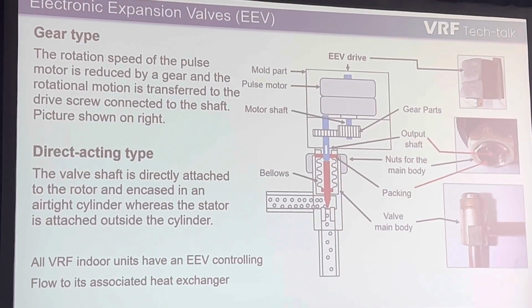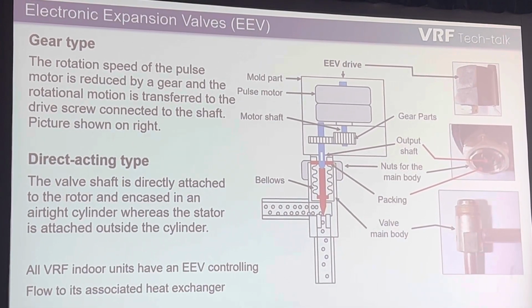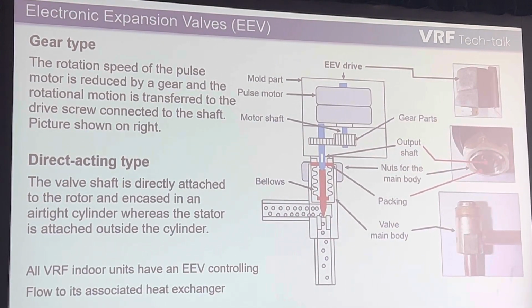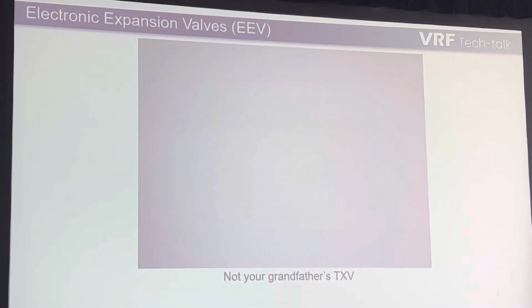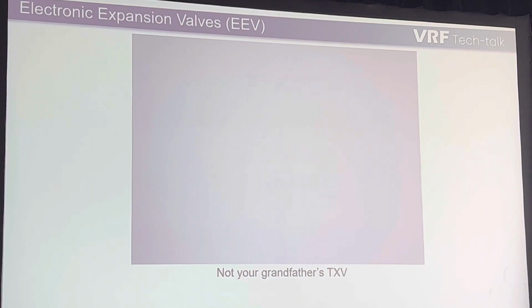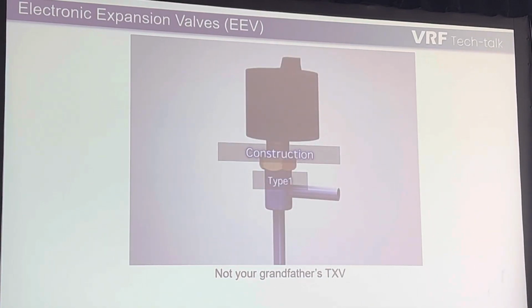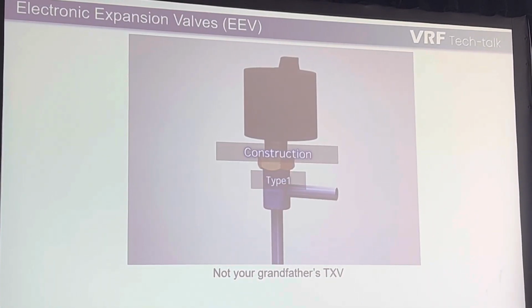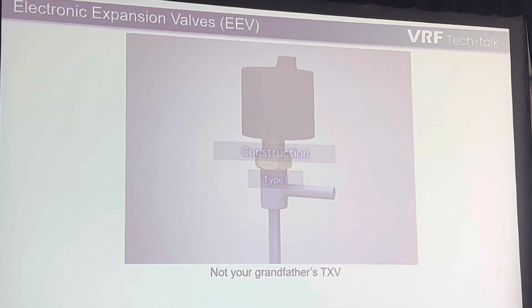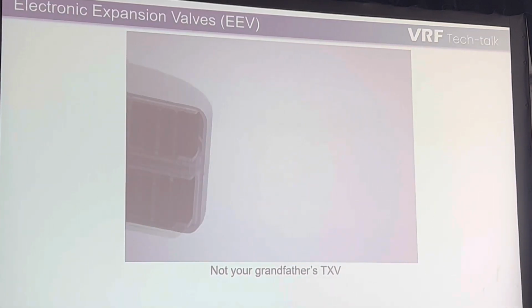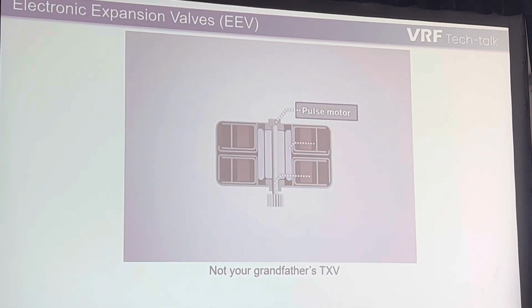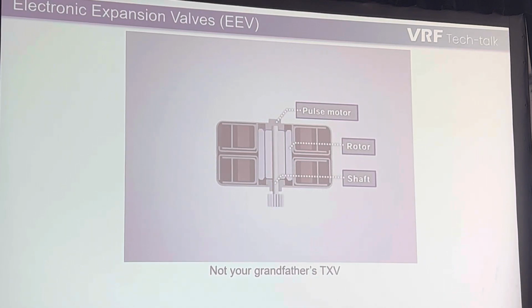Valve design. 2,000 pulses, 0 to 2,000. It's precise control on the indoor units and outdoor. And I've got another beautiful video for you. This is an animation sequence of what the actual valve looks like. Both valves, actually. We're going to talk about the gear driven, and we're going to talk about the non-gear driven, or the donut valve, as some people call it, or linear expansion valve, as others call it.